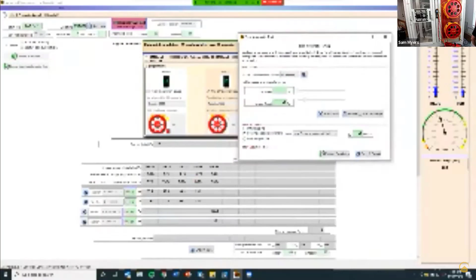And notice how it started two new rows for me here. So I had my data collected under that Range A, and now my data collected under Range B. So every aspect of the test will be in the report, from when you change ranges, pretty much everything that happened. So that point's completed. Now I'm going to drop it to 10, and this will be my last reading.